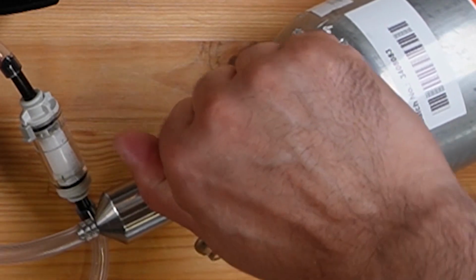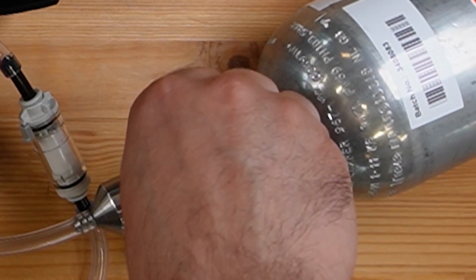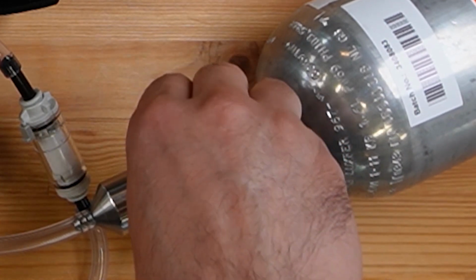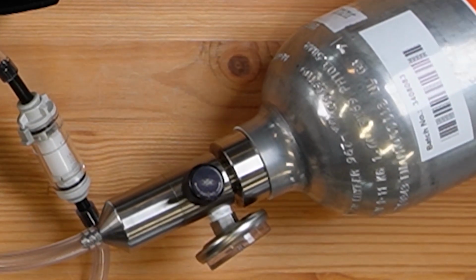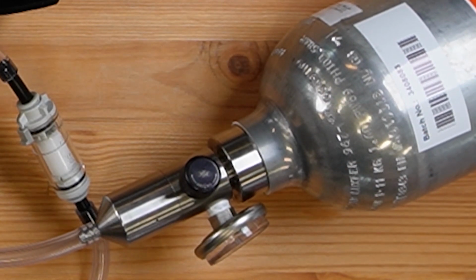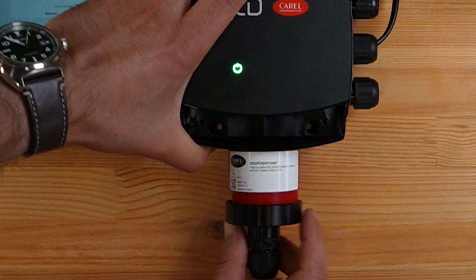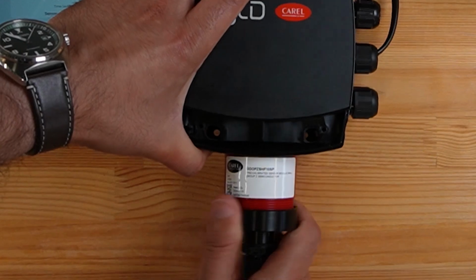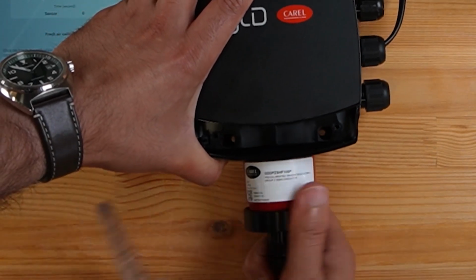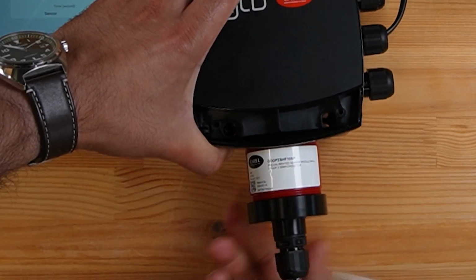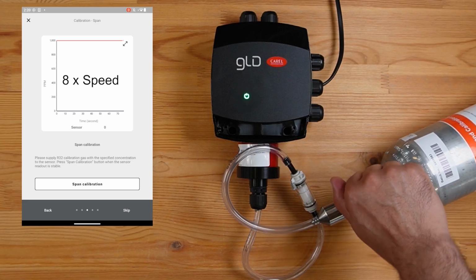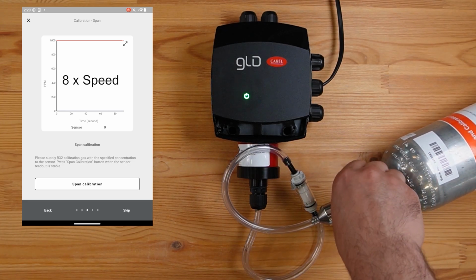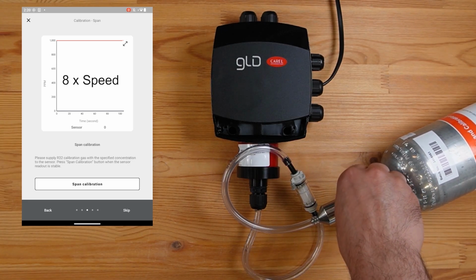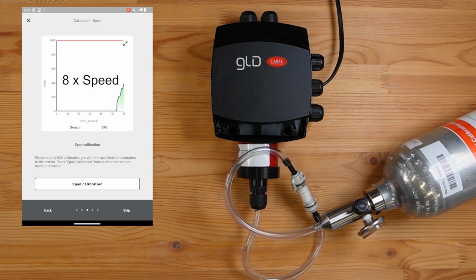Open the regulator on the gas cylinder to a flow of around 0.5 liters per minute, and let the gas flow for a few seconds without the calibration adapter connected to the sensor. Now mount the calibration kit on the sensor head. Screw it on firmly. Supply the gas at the known concentration using the calibration kit. Wait about 1 minute until the gas concentration stabilizes.